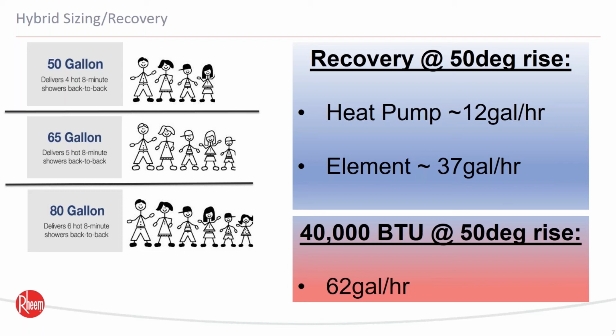So, with a 50-degree rise, so if your incoming water temperature averages about 70 degrees throughout the year, you're going to get about 12 gallons an hour of recovery just with the heat pump. So that means everyone's going to shower in the morning, they leave for work and school, unless they're in COVID land. And then that heat pump water heater is going to take 3 hours, 4 hours to recover all that morning usage. And it's going to do it efficiently. It's going to do it slowly.